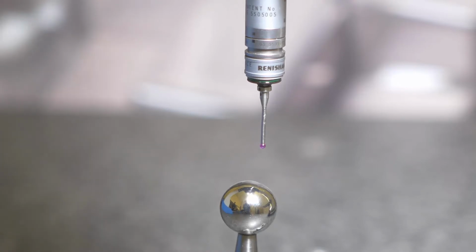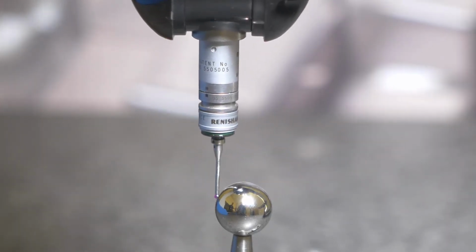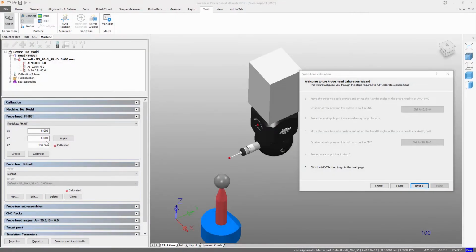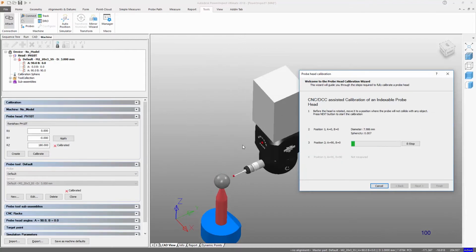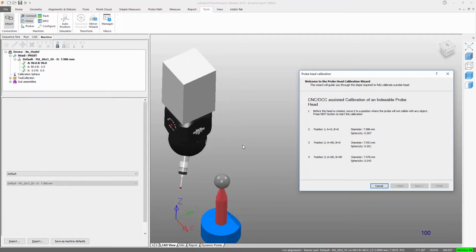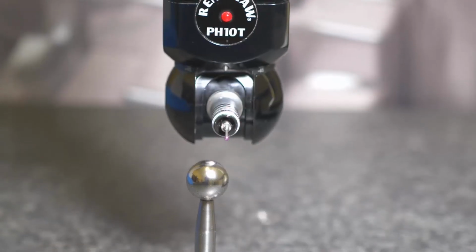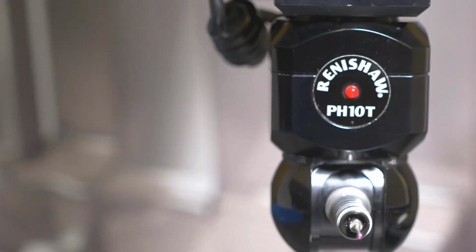Probe calibration on CMMs and manual devices as well as machine tools can be done in a multitude of different ways. This can be done from within PowerInspect or can be done directly in the protocol if doing calibration independently. This is usually the case when using the I++ protocol on that of CMMs. Calibration for CMMs in PowerInspect is done using the simple probe calibration wizard. This process ensures all necessary probe angles are calibrated before the inspection is carried out.